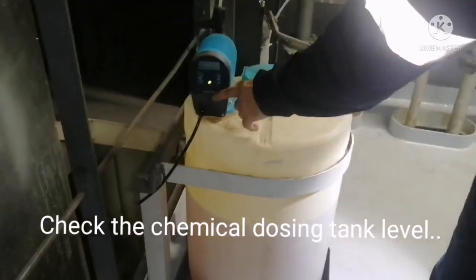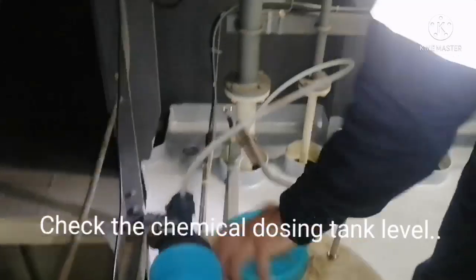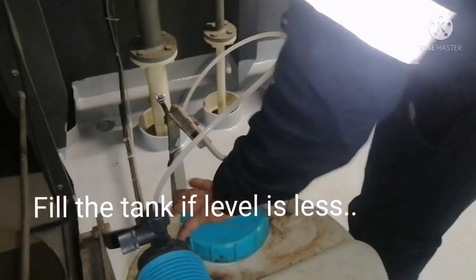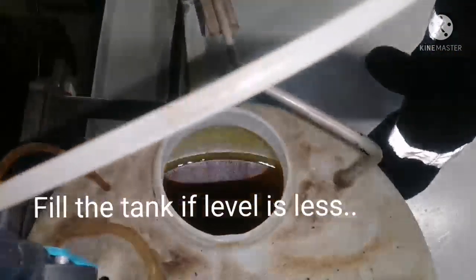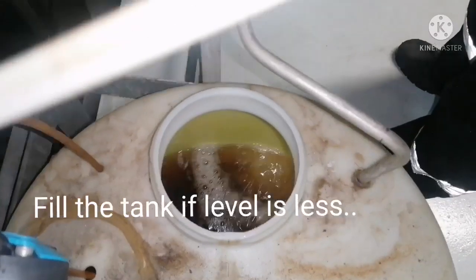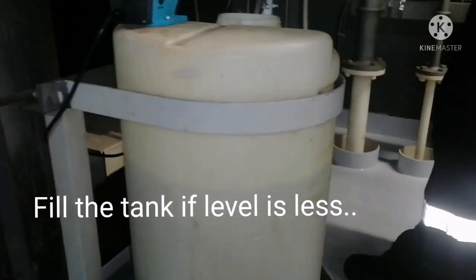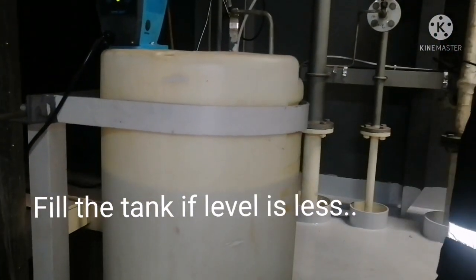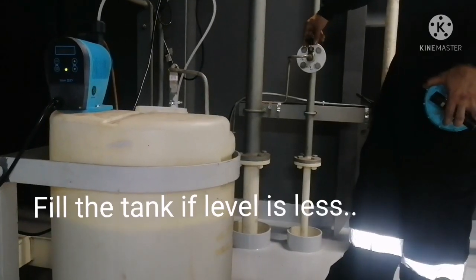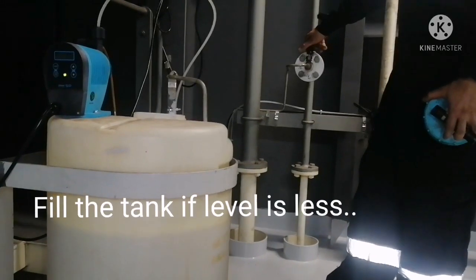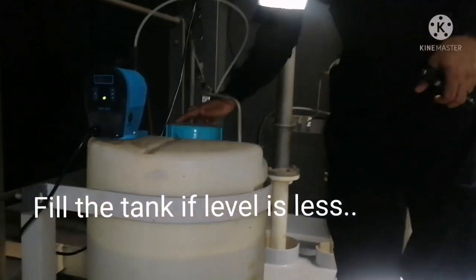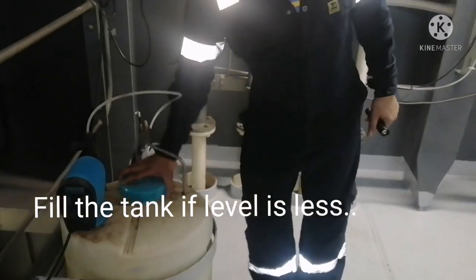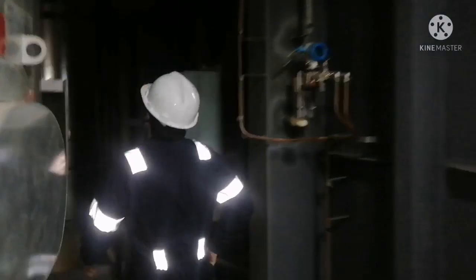Then you find the chemical dosing tank, and you have to check whether the dosing pump is running or not. And also you have to check the level inside the dosing tank. If the level is less, you have to fill the water by adding chemicals. So this is how you have to fill the water. Usually most of the ships have a direct fresh water line which connects to the dosing tank. So all you need to do is open the water, and you have to stand by there till the water level is achieved. If you open the filling valve and go for some other work, there are chances for you to forget the filling valve. So there are chances for the water to overflow from the dosing tank.